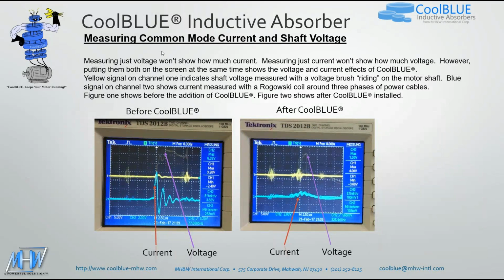So, measuring common mode current and shaft voltage. Measuring just the voltage won't show how much current. Measuring just the current won't show how much voltage. However, when you put them both together on the screen at the same time, it shows the voltage and the current effects of the CoolBLUE. For example, the yellow signal in channel 1 indicates the shaft voltage as measured with a voltage brush riding on the motor shaft. The blue signal in channel 2 shows the current measured with a Rogowski coil around the 3 phases of power cables.